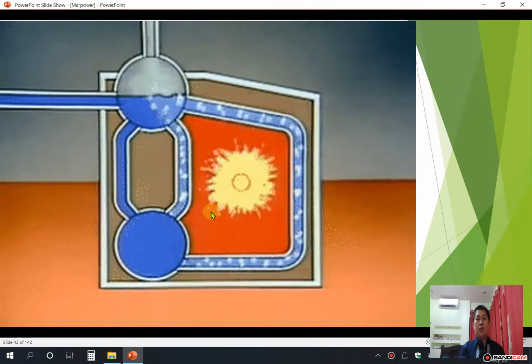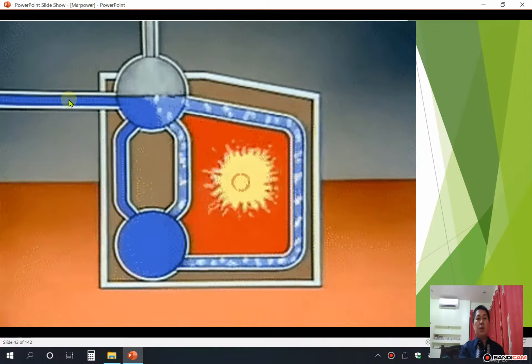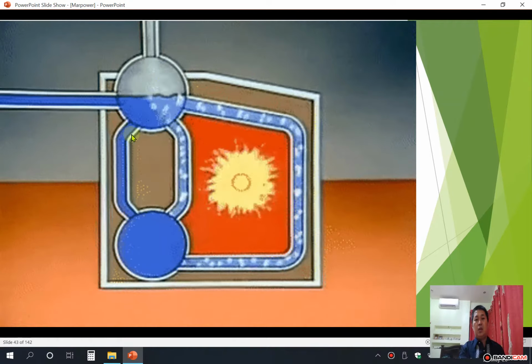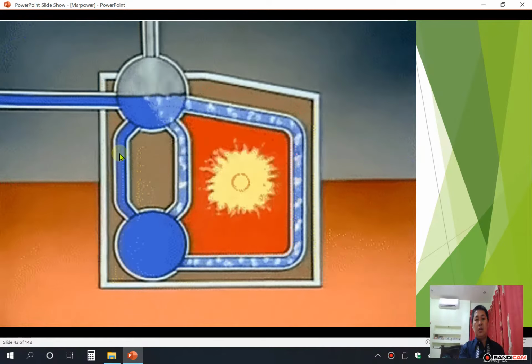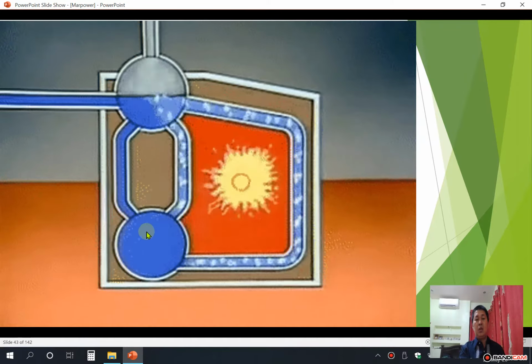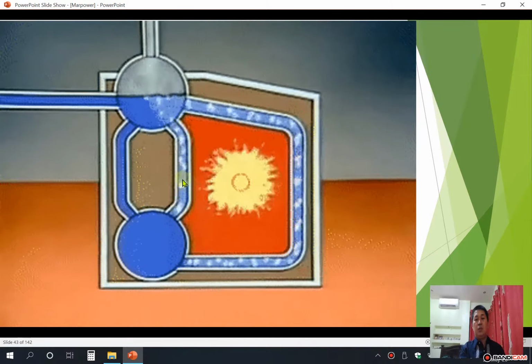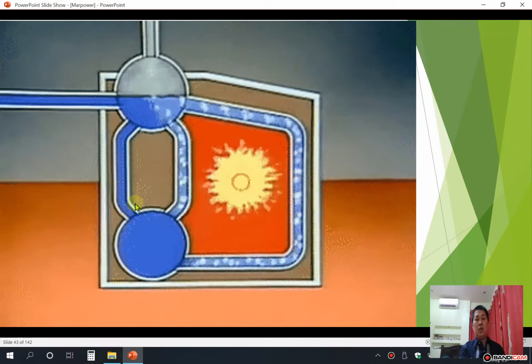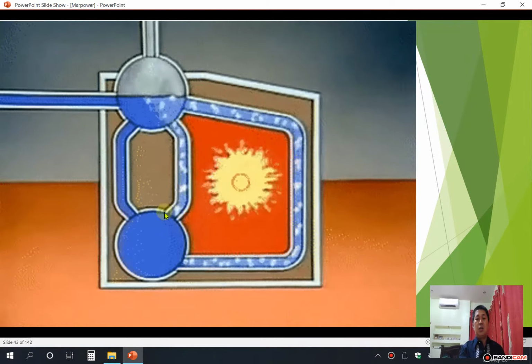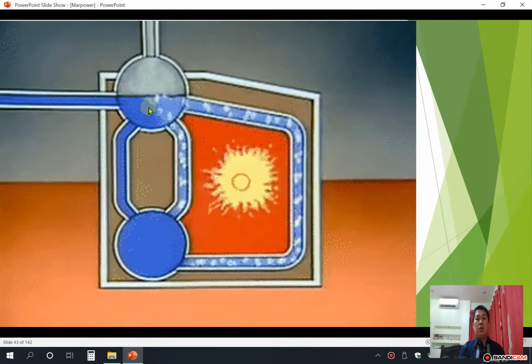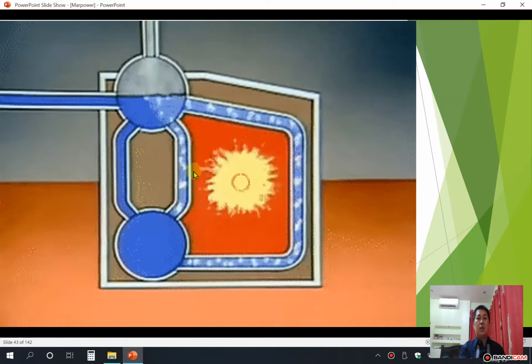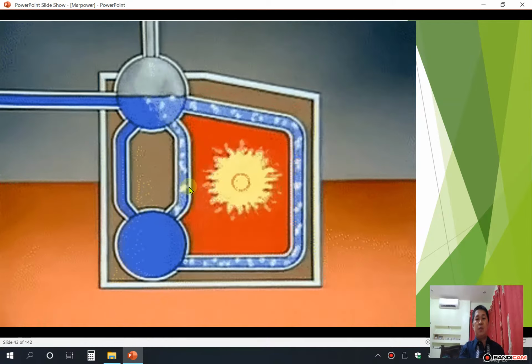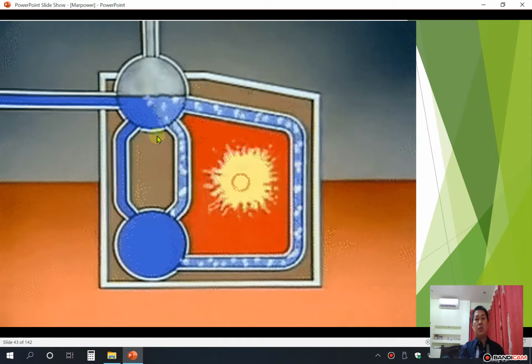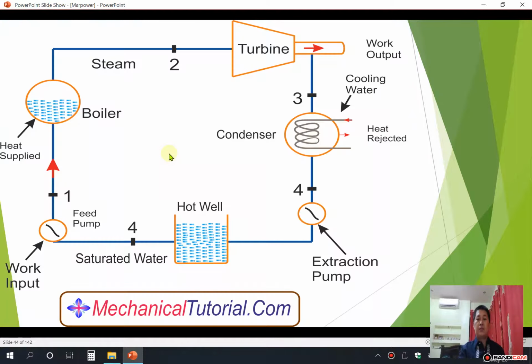So you have here your boiler. You have here the feed water inlet. It will flow through your downcomer. This is your water drum, boiler drum, and this is the riser. This is the downcomer. This is the riser. The hot water will go up there and produce steam. You have here the fire, the combustion chamber, to heat this water to generate steam. So this is the basic steam cycle.